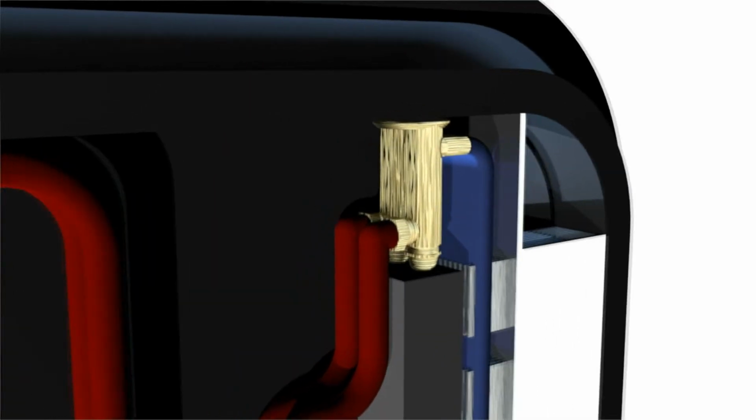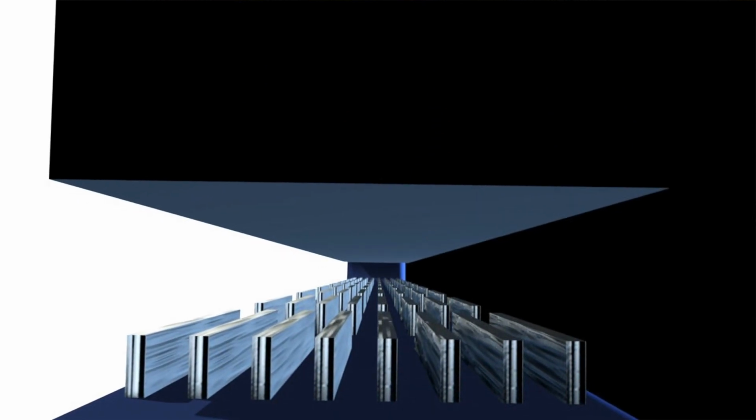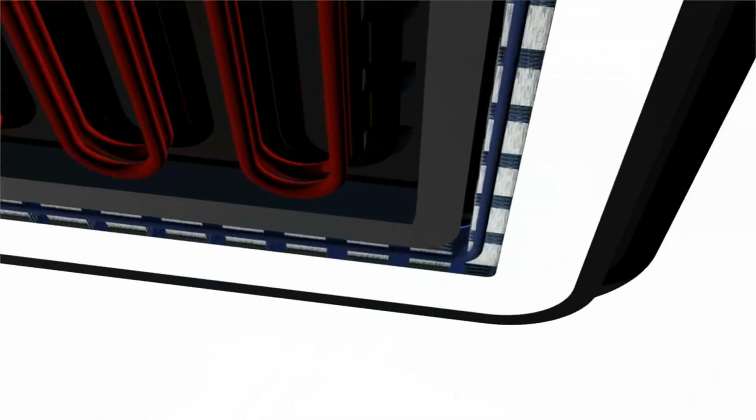Because of the speed at which depressurization occurs, half of the refrigerant is instantly evaporated into a saturated vapor. This mixed vapor and liquid refrigerant is then run through the evaporator coils that are connected to the cooling tunnel by aluminum leads. These leads allow the refrigerant to draw heat from the air inside the cooling tunnel to replace the heat dissipated into the environment by the condenser coils.